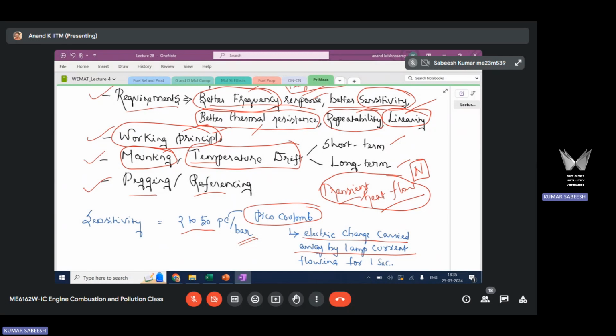Because of this thermal stress, with the temperature inside the cylinder continuously varying, this results in the expansion of the sensor elements, including the diaphragm. And this leads to something called signal distortion. The pressure output gets distorted because of the transient heat flow that creates continuously varying thermal stress on all the elements of the transducer.